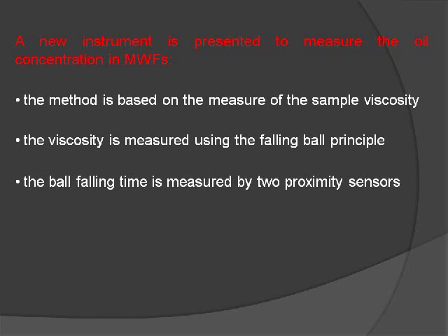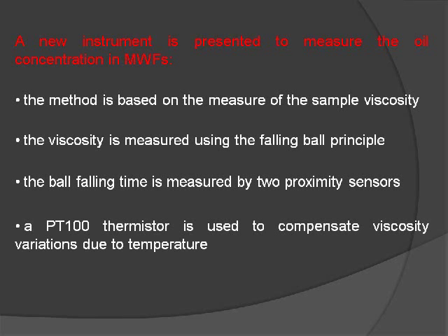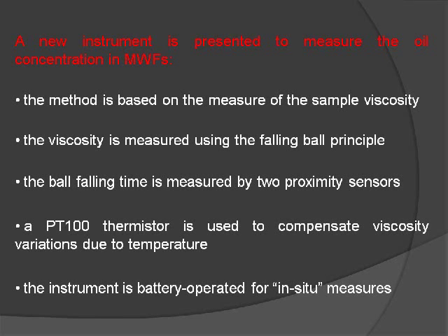The time required for the ball to fall between the top and bottom target points is measured by means of two inductive proximity sensors, detecting the presence of an electrically conductive body at a near distance of about 2 mm. The instrument performs the oil concentration measurement at environmental temperature and compensates for viscosity variations due to temperature using a PT100 thermistor. The lack of a controlled heating system results in reduced power consumption, as required for a battery-operated system. The instrument is battery-operated and suitable for in-situ measurements in metalworking plants.